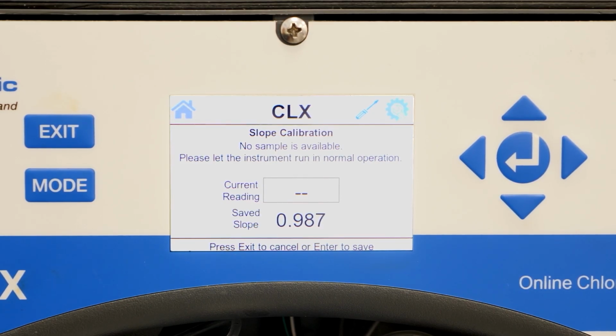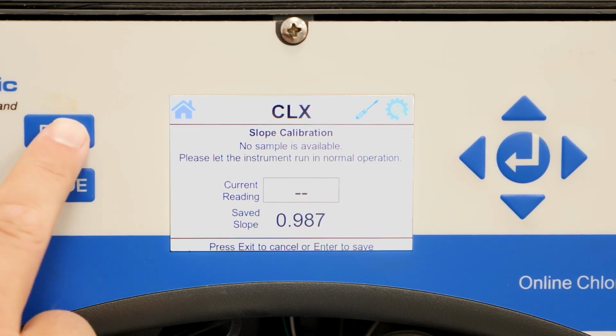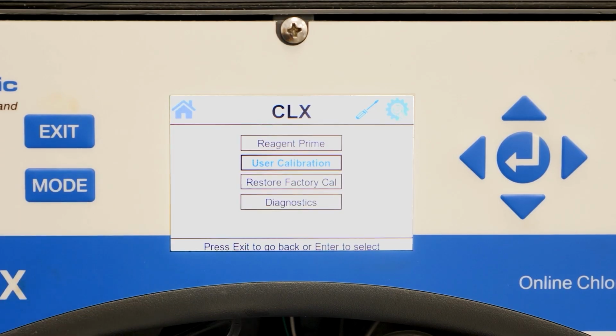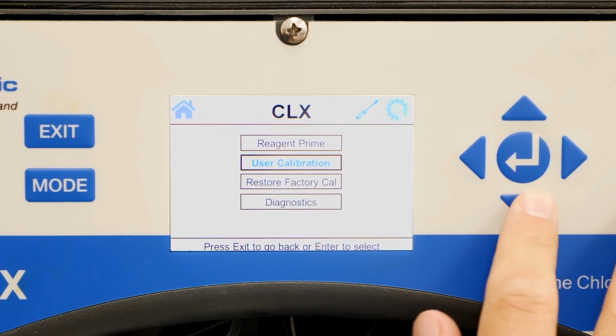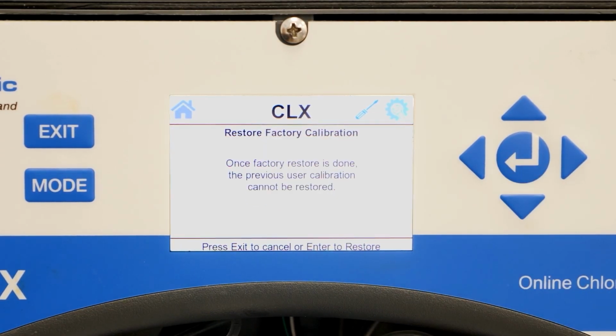This can be done by catching clear water from the drain off of the analyzer. Make sure to not take the sample when the analyzer is draining water with DPD chemistry in it. The next option is Restore Factory Cal. If you would like to restore the factory calibration because you believe an erroneous calibration has been stored in your analyzer, hit enter on the Restore Factory Cal. This is a new setting on the updated CLX that only restores the factory calibration.